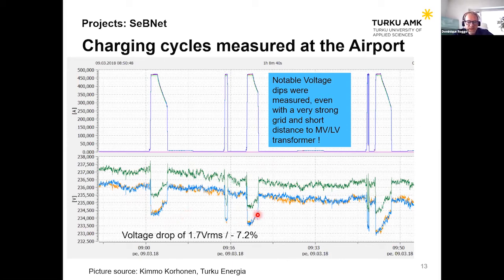Sorry, there's a mistake here. It's 0.7%, so it's below 1% voltage drop, a few volts, which is, of course, not a problem. But we are connecting directly to the transformer station less than 10 meters away.